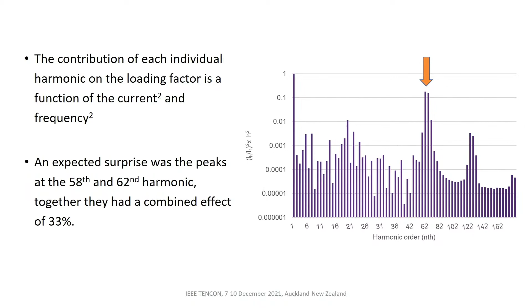Now, what we found, which was actually notable to us, was when we were looking at the harmonic order, we can see these two peaks. These are both around the 58th and 62nd harmonic. We found, surprisingly, that this was around the switching frequency of the inverters. But it wasn't a slow roll-off of harmonics from a few lower-order ones slowly disappearing down. They were becoming lower as we were moving along, and then all of a sudden, you've got these peaks. So then we were thinking, well, in terms of the transformer, what is it doing? And we found that together they had a combined effect of 33% extra heating. So we thought that was actually quite surprising.